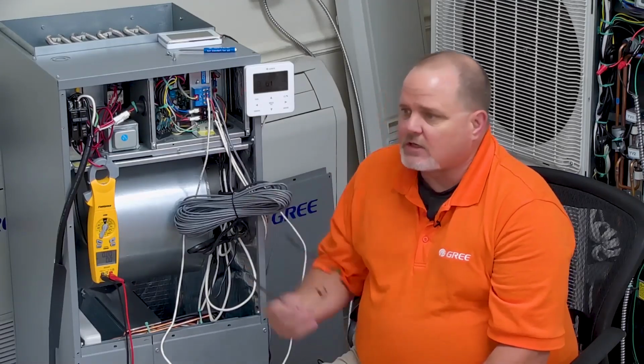So there was a little bit of hesitation with some buyers that not having the electric heat function, and if the heat pump should go down, they don't have that backup feature that they were used to. So there was some hesitation to buying the MultiPro equipment because of that. So with this, that's going to resolve that issue. And then even if that heat pump goes out on an error code, you still got electric heat until you can get somebody out there. Now I will say, our downtimes to the MultiPro units have not been bad. Normally when they're down, a guy can get out there and get it back up and running fairly quickly.